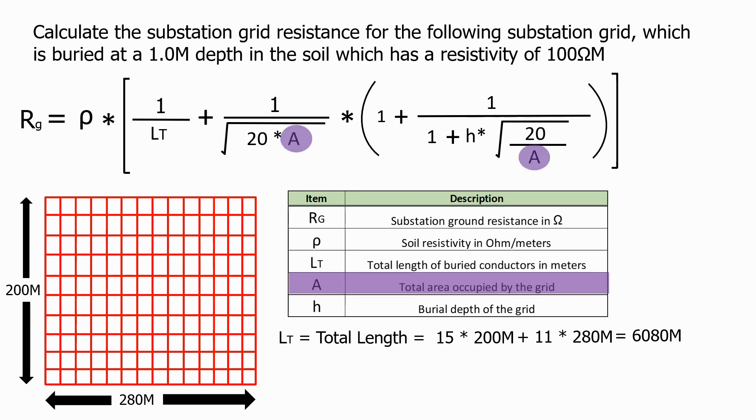Next we have A, which is the area. This is simply the width times the length of the grid, equals 200 metres by 280 metres is 56,000 square metres. The other parameters we know: h, which is the buried depth, is 1 metre. And ρ (rho), which is the soil resistivity, has a value of 100 ohm metres.